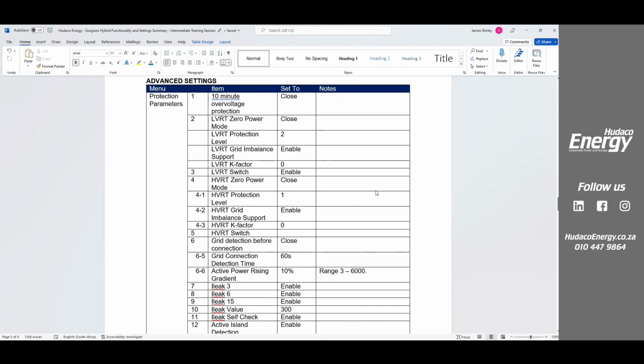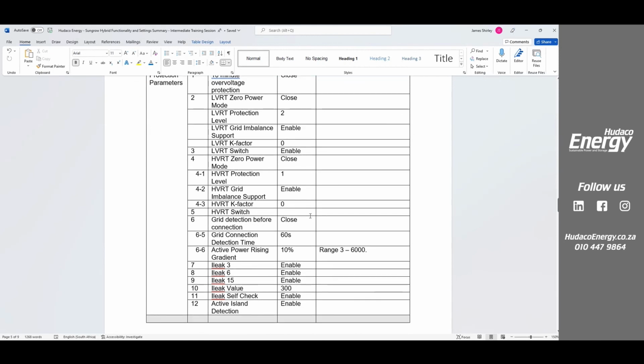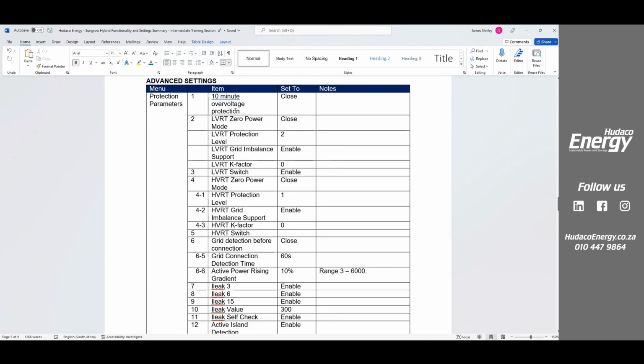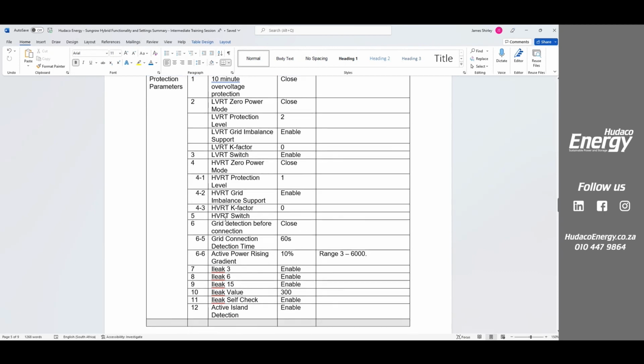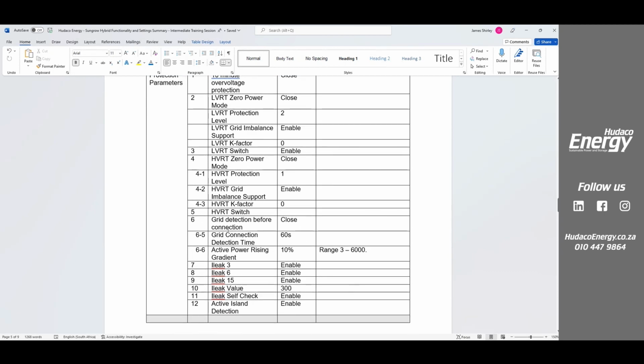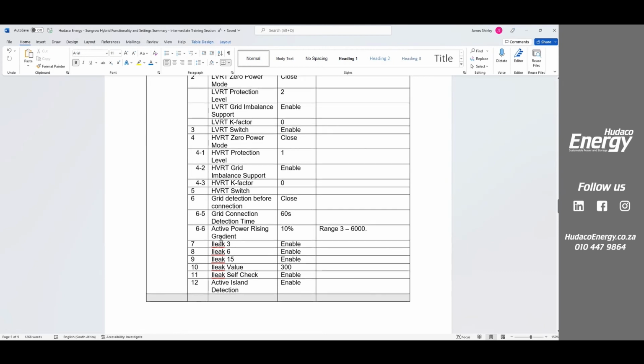Okay, so on the protection parameters, you see how many different things we can look at here. So 10-minute over voltage protection, low voltage ride through, high voltage ride through, grid imbalance. Are we actually detecting the grid before connection? Here's this grid connection time is 60 seconds from NRS. This active power rising gradient, how fast do we want our panels to respond so that once the system starts up, do we want them to come up slowly or do we want them to come up faster?